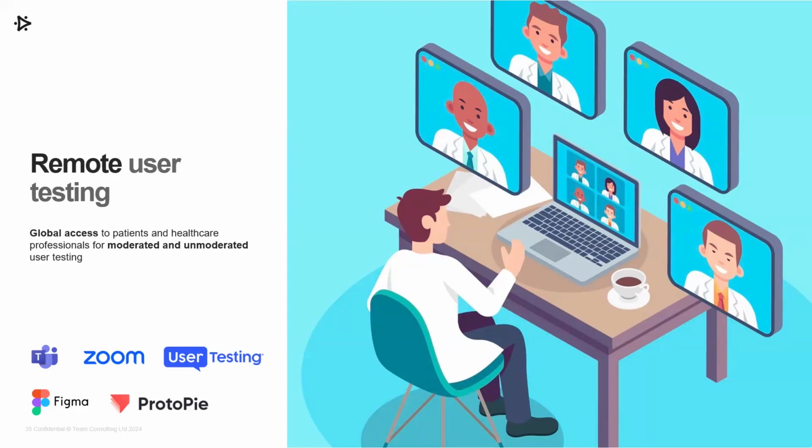It also allows us to recruit more quickly and at a lower cost, and we can ask participants questions about their environment and how it affects their interaction with medical products. For digital products, we're starting to see more use cases for unmoderated remote testing that helps design teams to test rapidly and efficiently. It's not so common in developing medical products, but it is gaining traction. Just to emphasize that in-person simulated use testing is still the gold standard, especially for HF validation, but these other approaches can be incredibly useful, especially at the early stages of the design process.